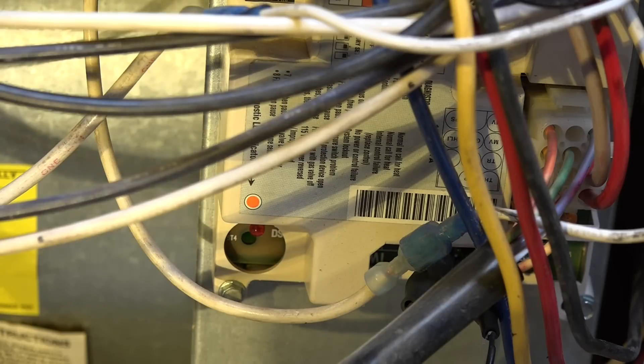Now it's going to keep that inducer on for a while and we're just going to kind of let this thing time out because it's eventually going to shut itself off because it's essentially given up on the pressure switch ever making.